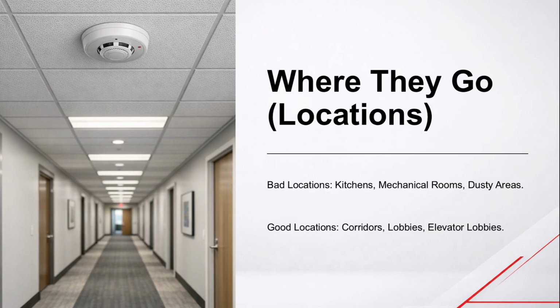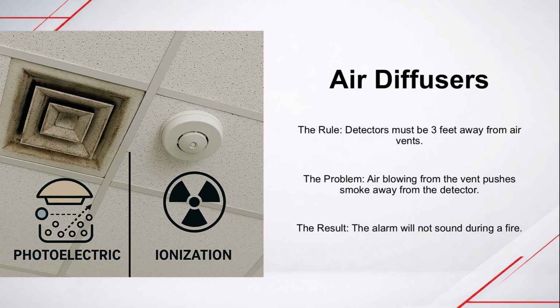Smoke detectors are primarily used for life safety. You will typically find them in corridors, lobbies, and common areas. They are also critical in elevator lobbies to trigger elevator recall. However, they are not appropriate everywhere. You should never install smoke detectors in kitchens, bathrooms with showers, or dusty mechanical rooms, as environmental factors will cause constant false alarms. This leads us to the absolute number one mistake I see on inspections: airflow.